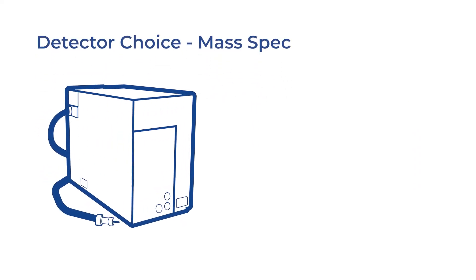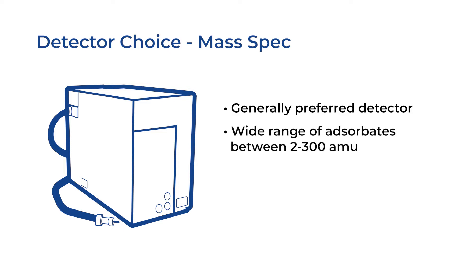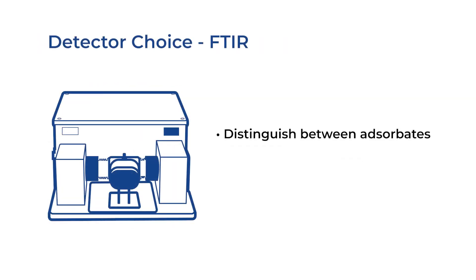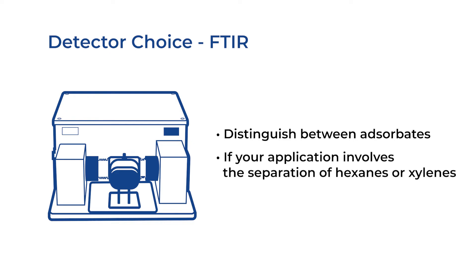Mass spectrometers are generally the preferred detectors. They offer a wide range of detectable adsorbates between two and three hundred atomic mass units and have excellent detection limits down to single digit parts per million. Additionally, it is a fast and accurate technique. Alternatively, FTIR can be used to distinguish components with the same atomic mass number, which cannot be achieved using a mass spectrometer.